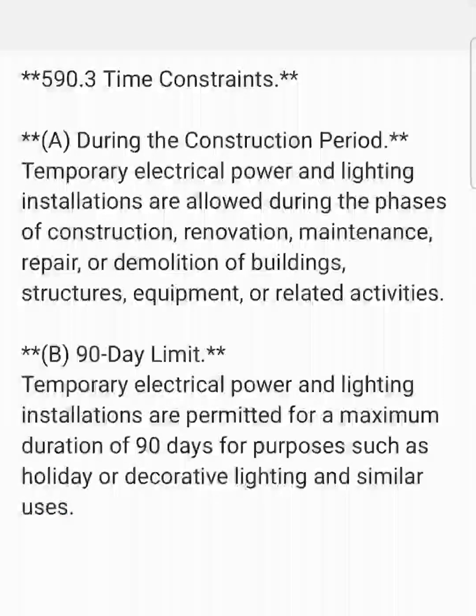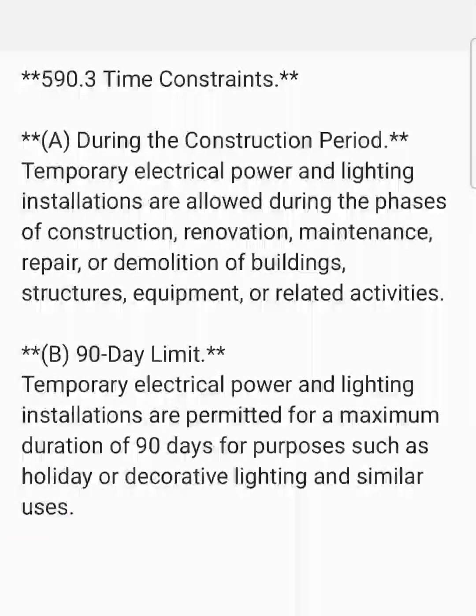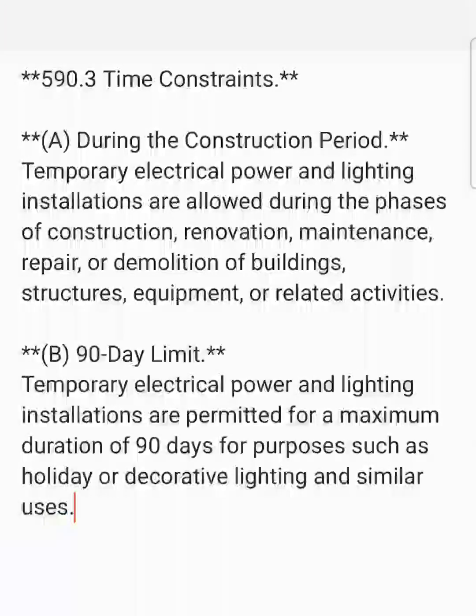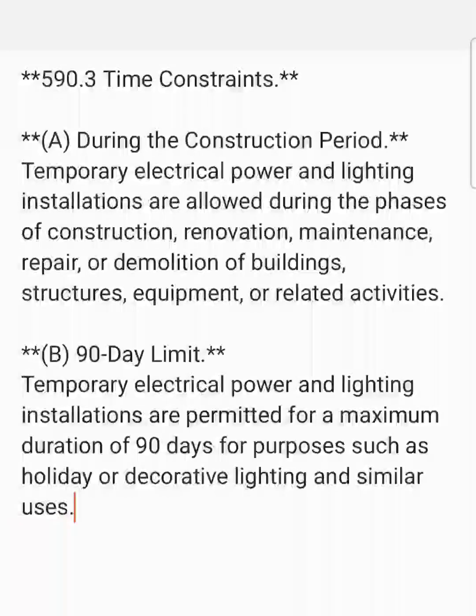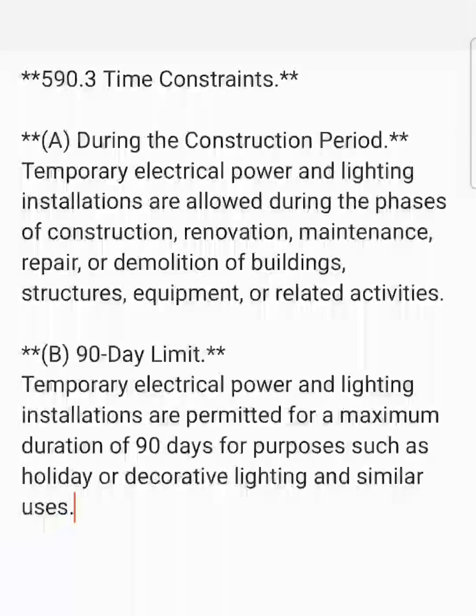In Part B, it talks about the 90-day limit. Temporary electric power and lighting installations are permitted for a maximum duration of 90 days for purposes such as holiday or decorative lighting and similar uses.